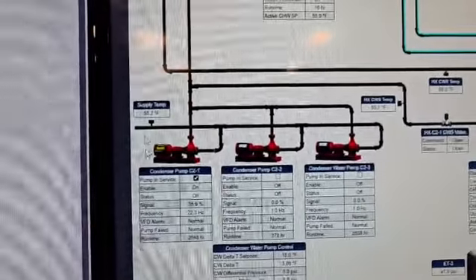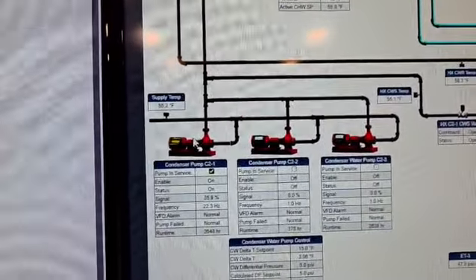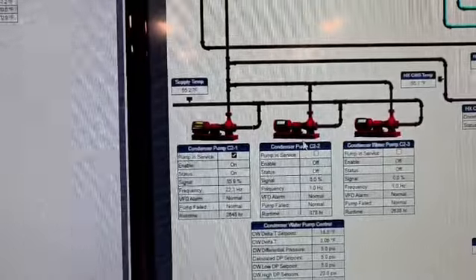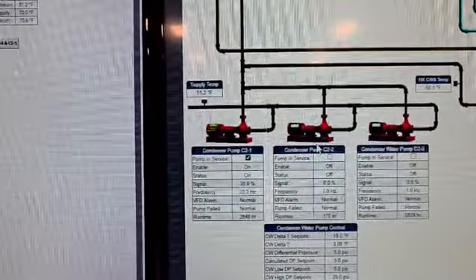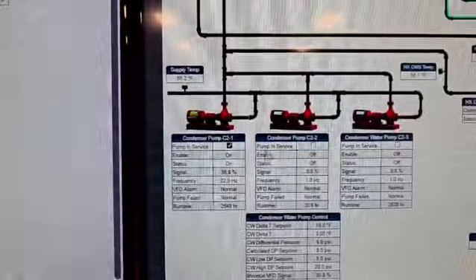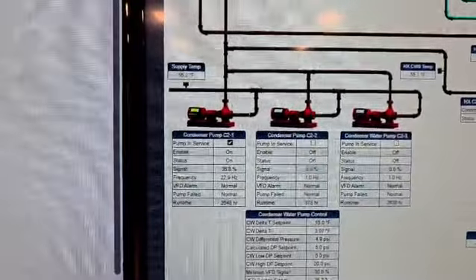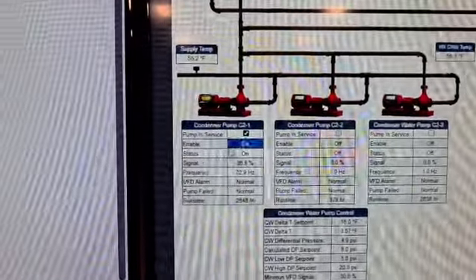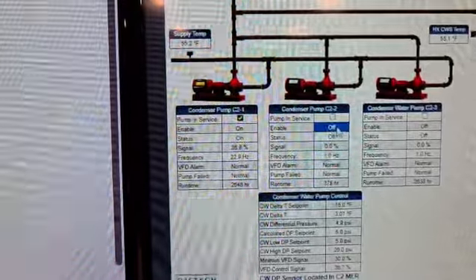And then you have 3 pumps, but this is all redundancy. If one goes down, the other one turns on. Or maybe during summer you need to move water a little faster, so you could enable more. That's all programming. The only thing you need to worry about is that the enable is on and the status is on. If the enable is on and the status is off, something is wrong.